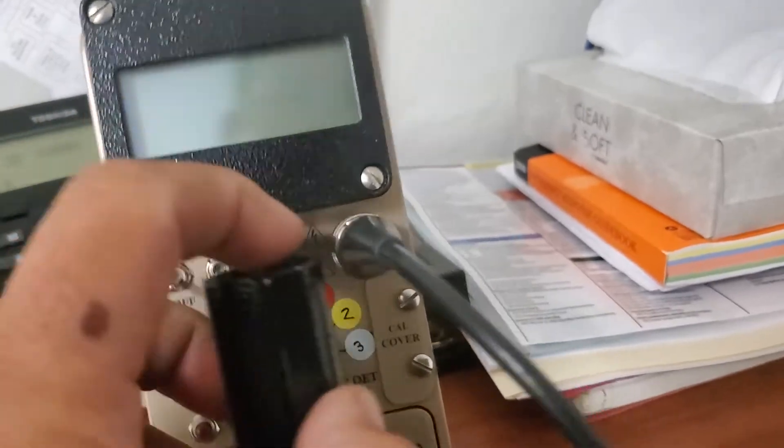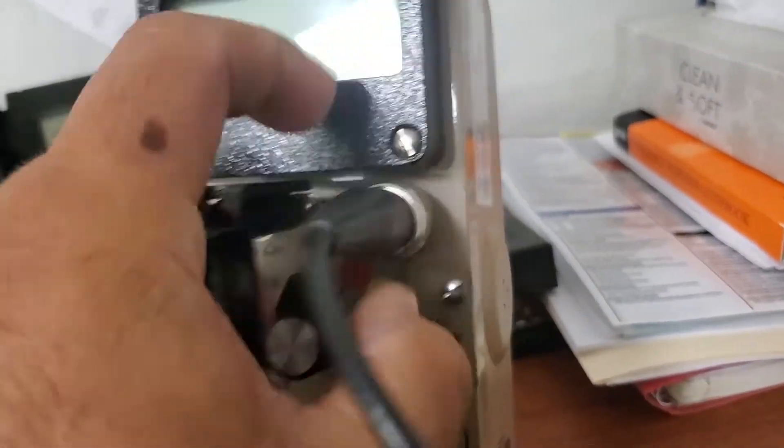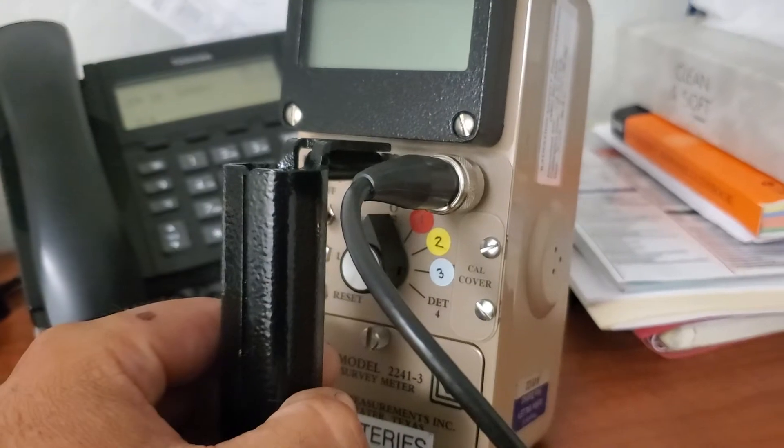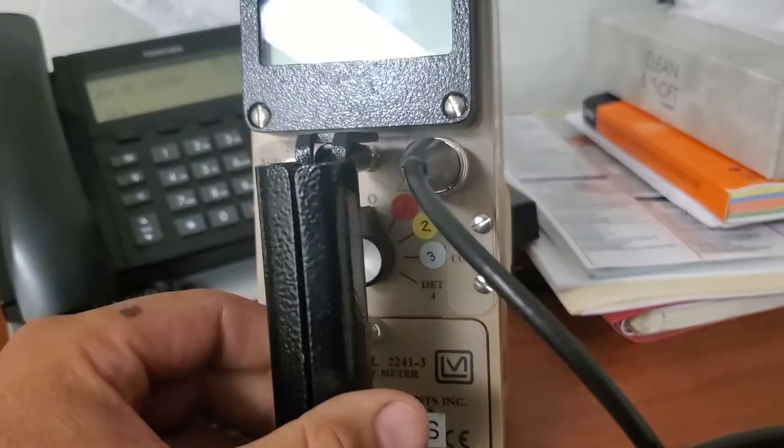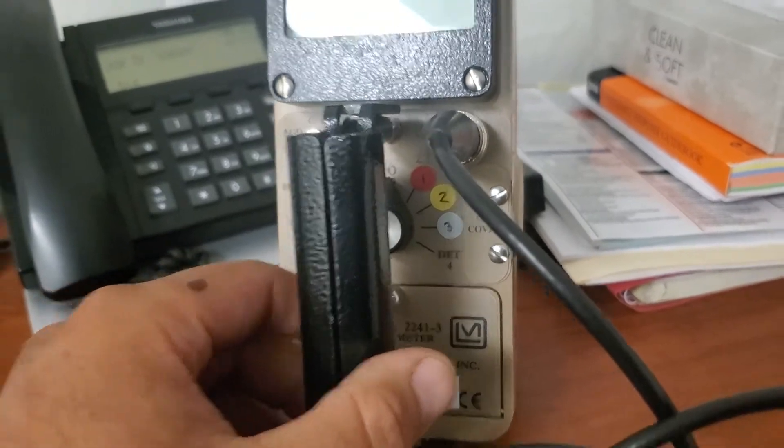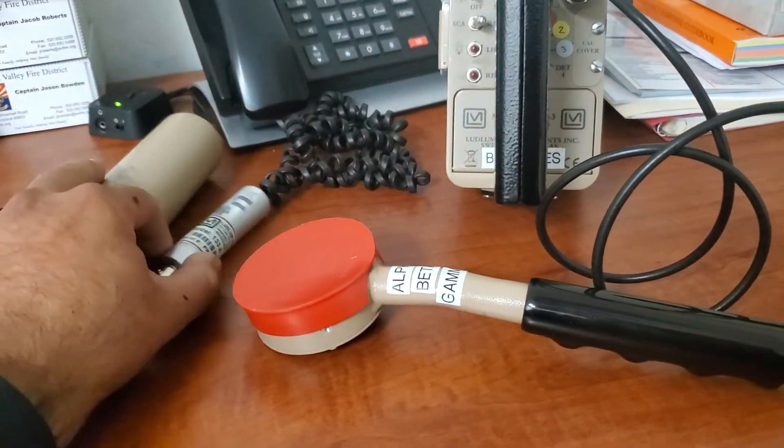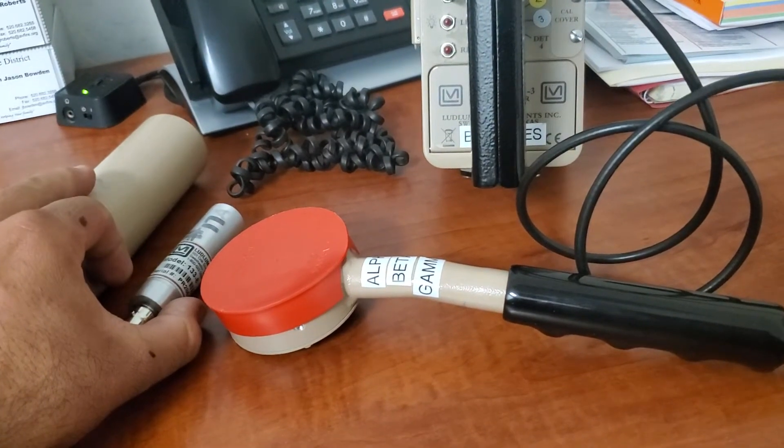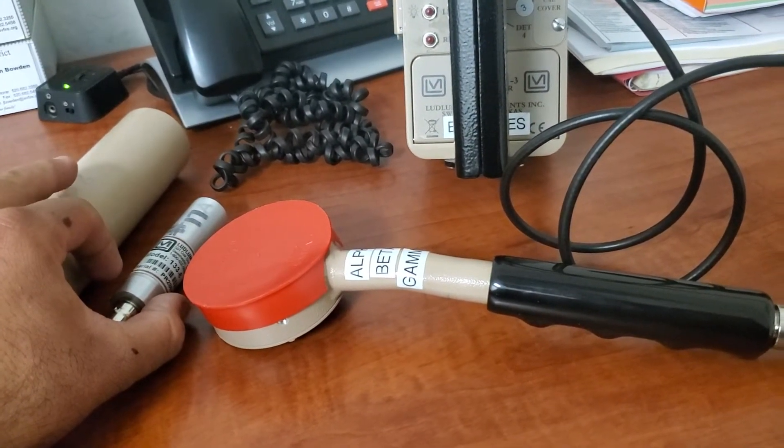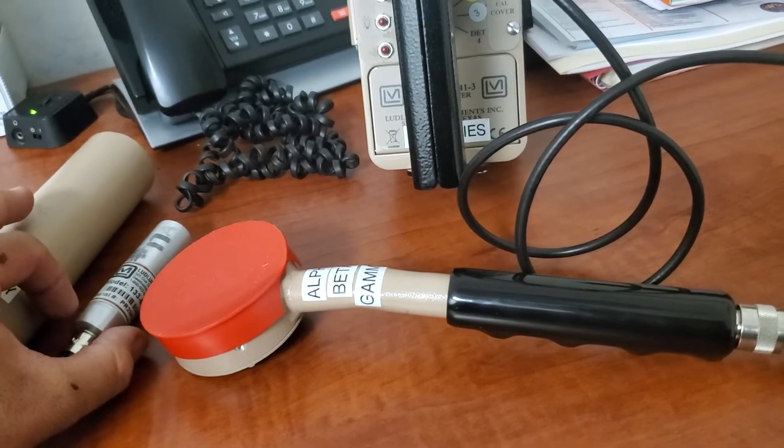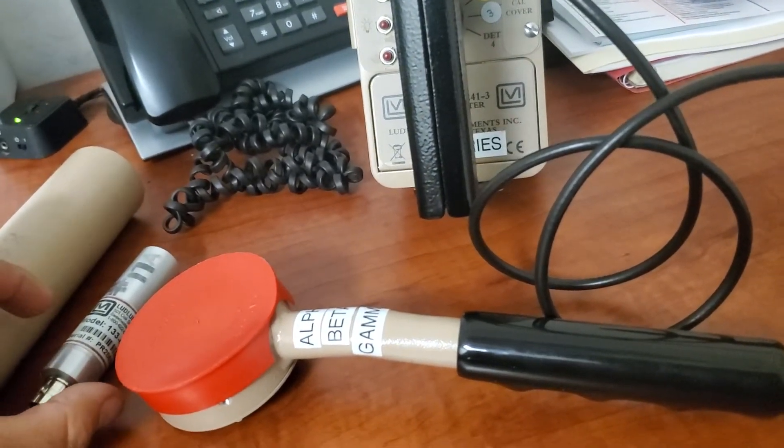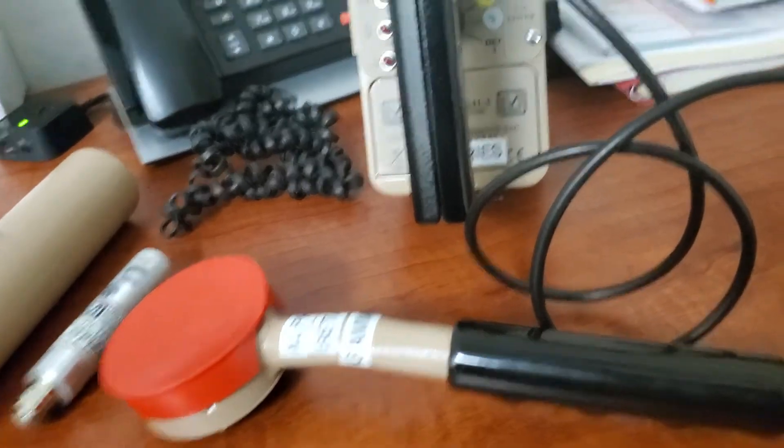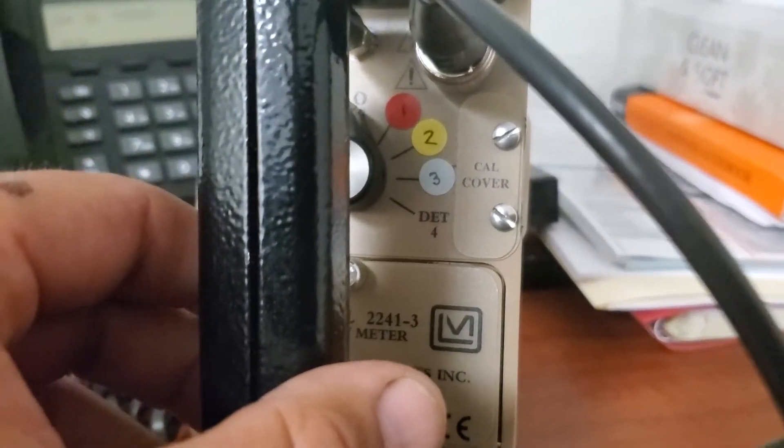Right here is where the cable plugs in and it has a little twist lock. One thing to note is that the cable and probe has to be plugged in prior to turning on the meter. Each one of these three probes uses a different voltage coming from the meter. So by incorrectly using the probe, you have the chance of getting an incorrect reading and or damaging the meter and or the probes.